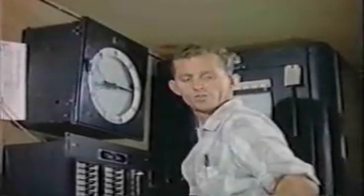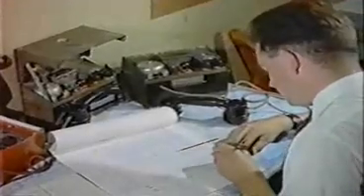With the welding completed on number 1 vessel, it was stress relieved by a system of internal electric heaters. Attached to the vessel are hundreds of thermocouples which record the temperature rise and fall over the whole surface and transmit their readings back to a system of recorders at a central control point. By this means, a graph can be produced which shows how each small section of the vessel behaved during the heat rise and during the cooling, which is allowed to happen naturally afterwards.